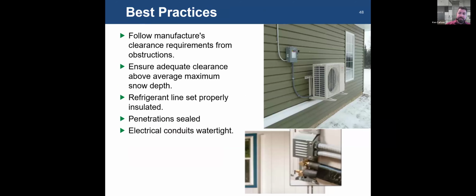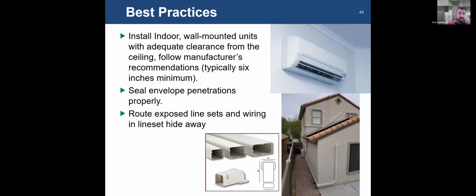Just some best practices, in summary, I should say. Follow your manufacturer's clearance requirements and instructions. Ensure adequate clearance for maximum snow depths. Make sure your refrigerant line sets are properly insulated, properly installed, covered. Make sure your penetrations are sealed. Make sure all your electrical conduits outside are watertight. For your indoor units, make sure you have the proper clearances. Any wall hung units, make sure you have the proper clearance above the unit itself. The manufacturer will tell you what the minimum clearances are. Make sure you seal all your envelope penetrations properly.